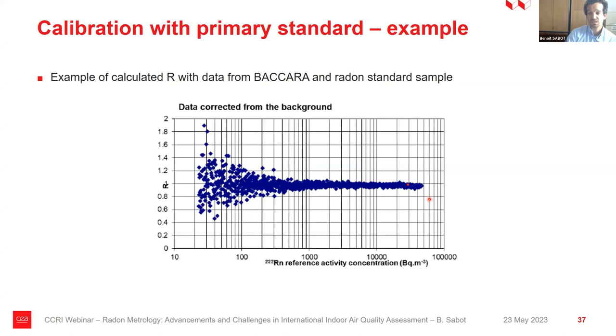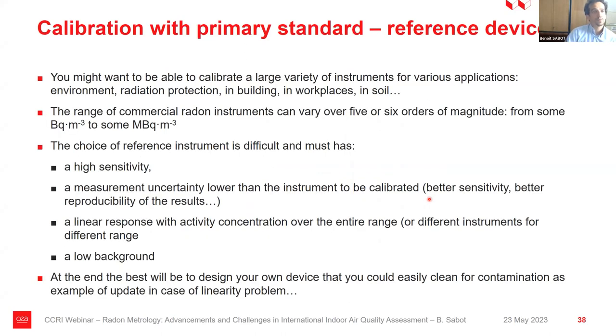However, as I said, it's time consuming, especially in terms of radon exposition time, because we typically do that for more than a month. So that means the device is inside the chamber for more than a month and you gather all this data. So that's why this technique is very useful for what I will call a reference device, a device that you will calibrate with primary standard and that then you will use to calibrate many detectors but with fewer calibration points.